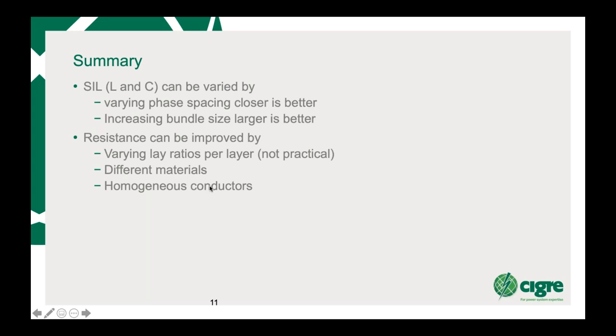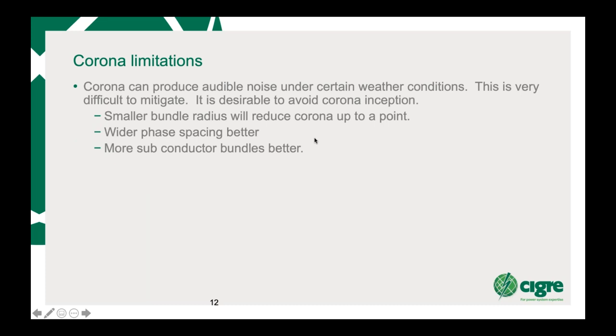Now we get into the next problem. What happens when we bring our phases closer together? The problem is that you start hitting corona limitations. And what's the problem with corona? It's not really losses on AC lines. It's more the audible noise that you can get under certain weather conditions. And it's very difficult to mitigate. So it's desirable to avoid corona inception.